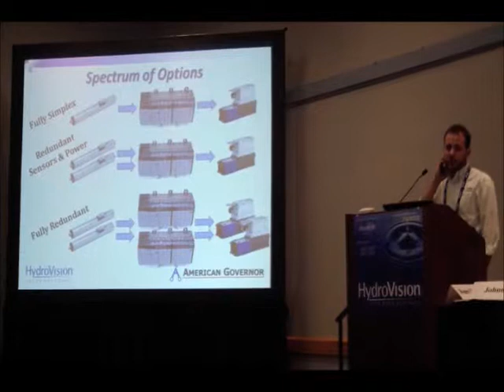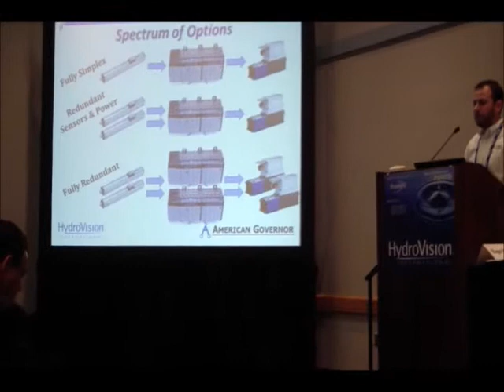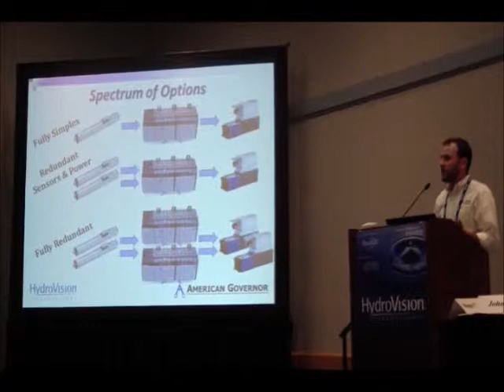for installing control systems, ranging from a fully simplex system where you have single inputs, single power sources, going into a single controller, driving a single set of outputs. A little more complex, maybe you have redundant sensors, redundant power supplies, redundant power sources, all still going into a single controller, which has a single set of outputs. And then finally, fully redundant control systems where you may have multiple sensors going into multiple controllers, which are comparing data or voting, and then sending control signals to maybe multiple outputs, which are in a passive configuration where you have a primary and a backup control system.